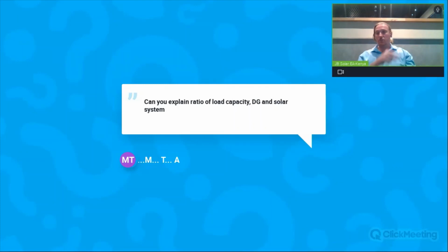So it depends on your load. What does your load look like? Are you consuming in the morning, the evening, or the middle of the day? That's your potential for consuming the solar energy. We also have to consider the diesel generator at 30% minimum load, so we want to keep it at 30% or all the way off.